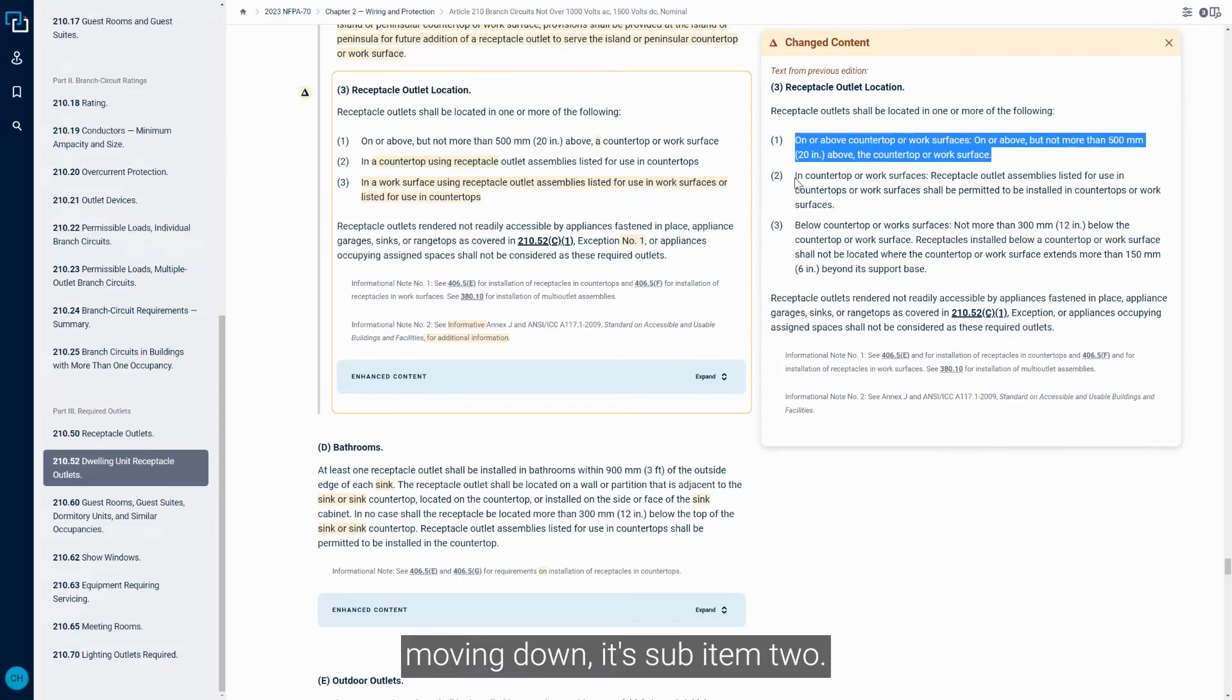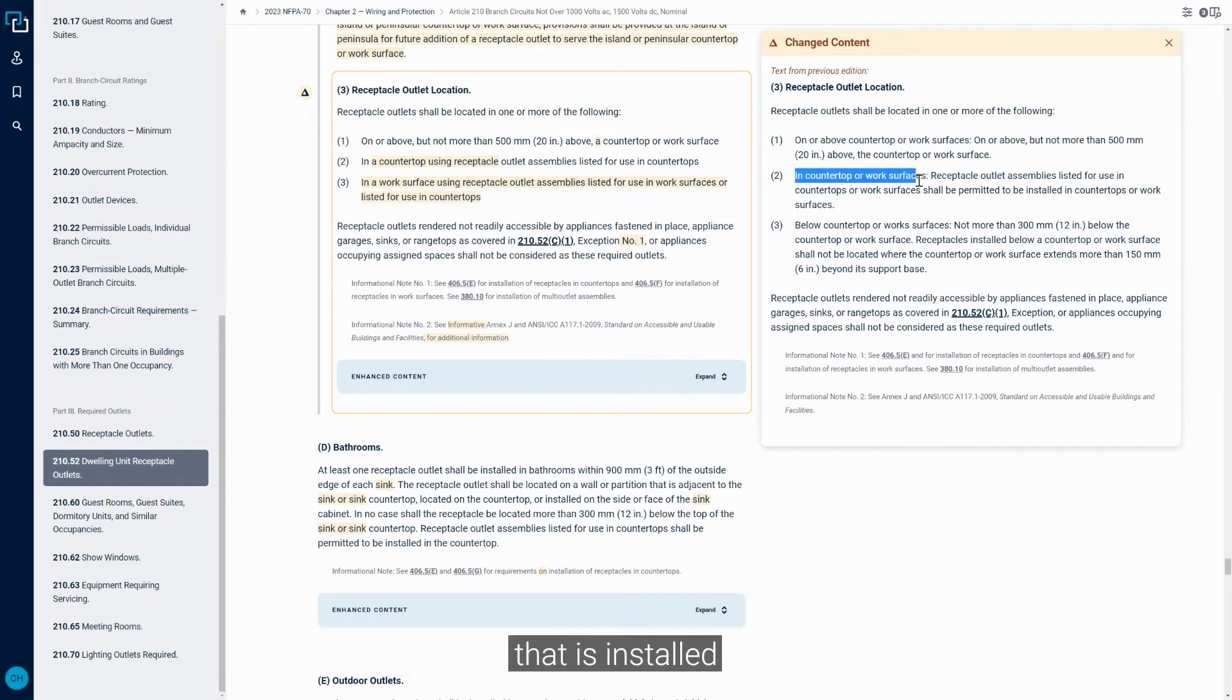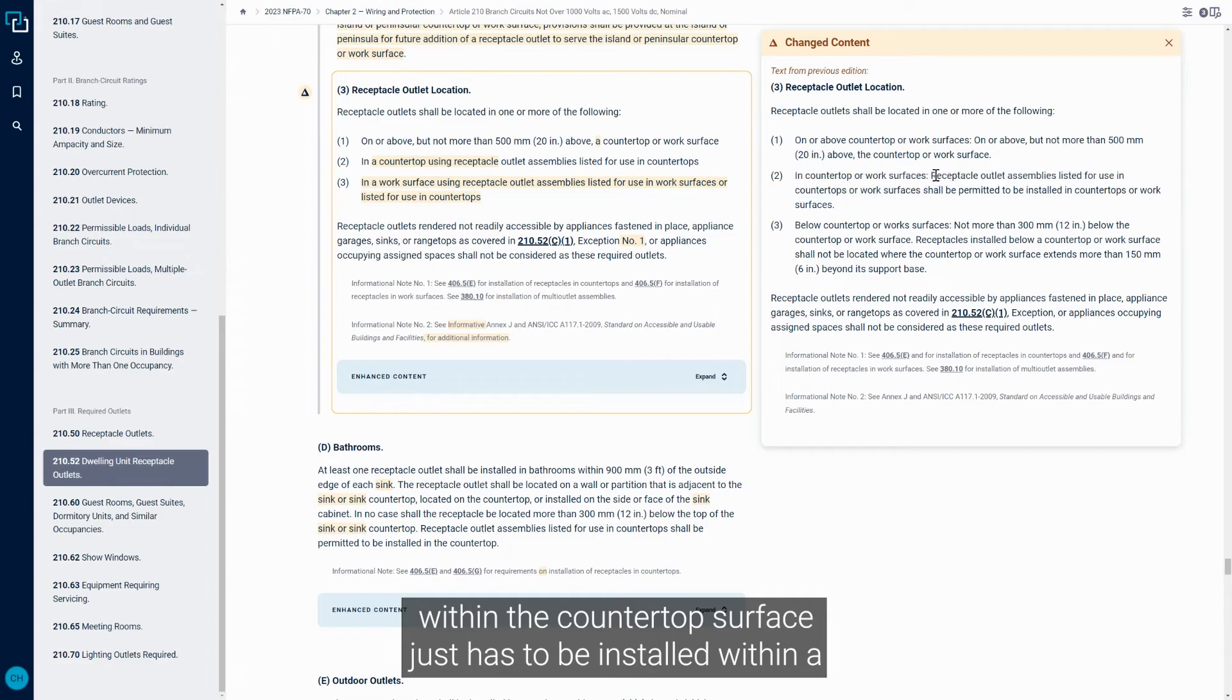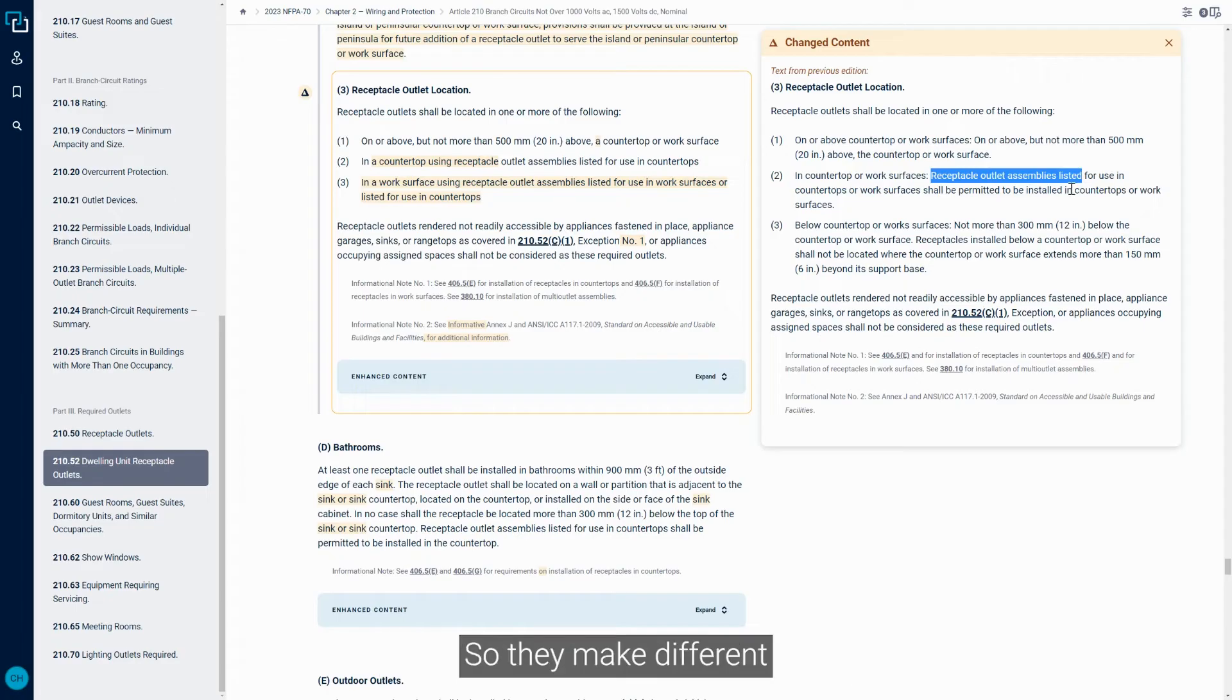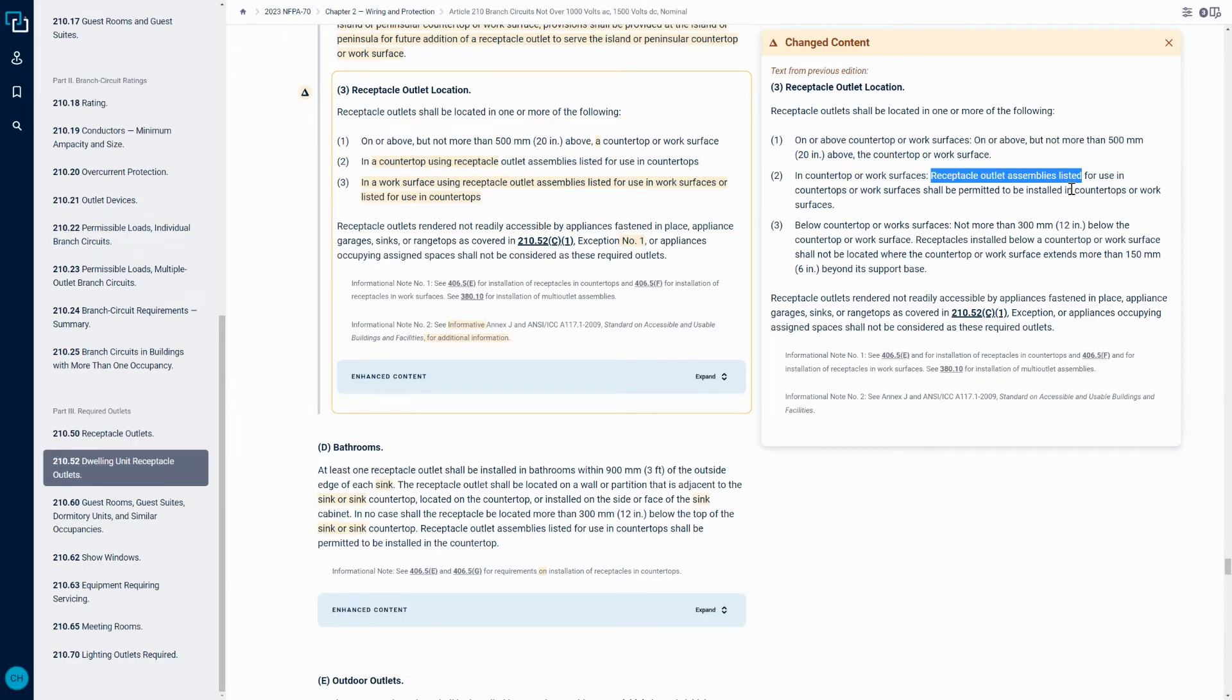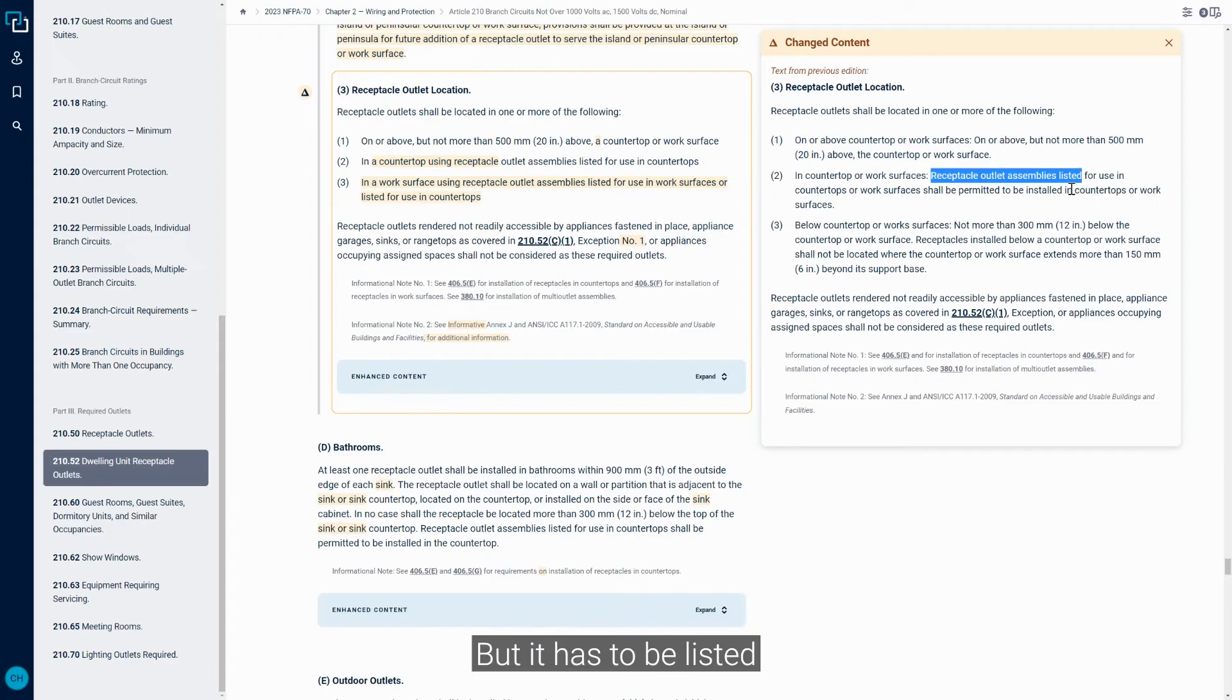Moving down to sub-item two in the 2020, it could be installed in countertop or work surfaces. So a Receptacle that is installed within the countertop surface just has to be installed within a listed outlet assembly in that case. So they make different pop-up type outlets that can be mounted right within the countertop that you can utilize in these applications now, but it has to be listed in order to be utilized.